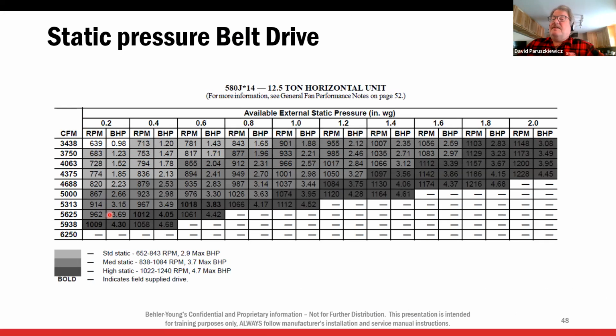So the medium static, which is the medium gray here in the middle, if you look at this 5,000 CFM unit, that unit is good for, if I follow this across, 0.8 inches of static. All right, everybody see that? If I have 1 inch of static, I have to go to the high static unit. Now the motor's the only difference. So, if I'm working on a medium static unit, I look on this chart and I have 5,000 CFM and I have 1.2 inches of static, I need to change to the high static drive motor. The pulley will not adjust enough.